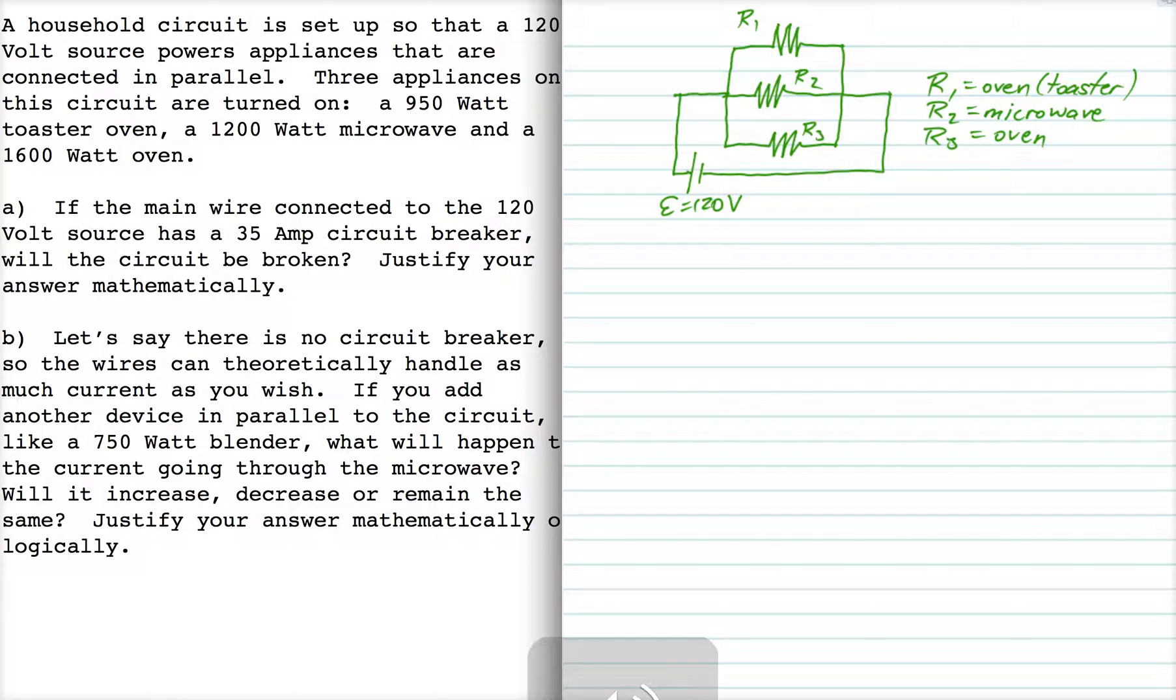All right, so what we need to do first is we need to figure out if a 35 amp circuit breaker in this line is sufficient. So we need to find out what this current is going into this junction. To do that, we need to find the three currents coming out of that junction. We need to find I1, I2, and I3.